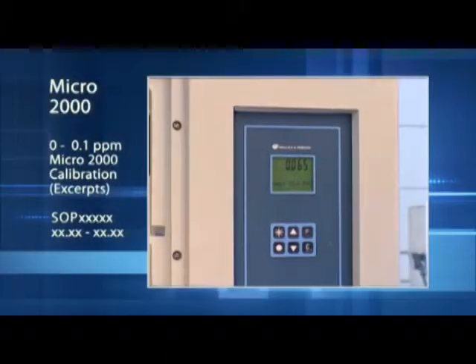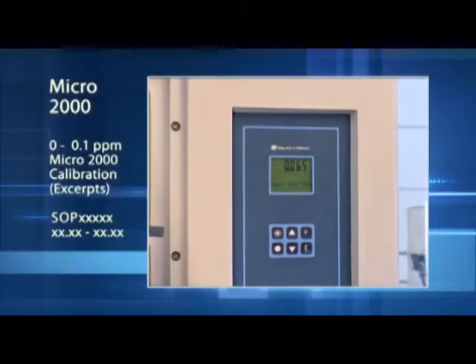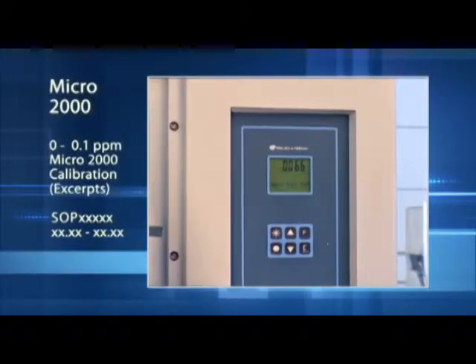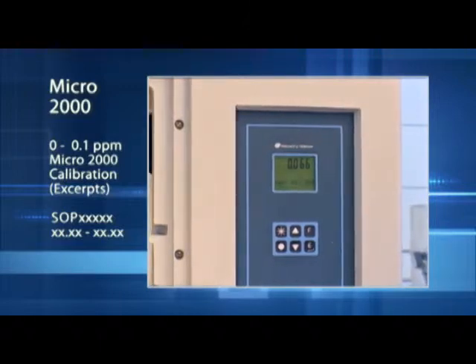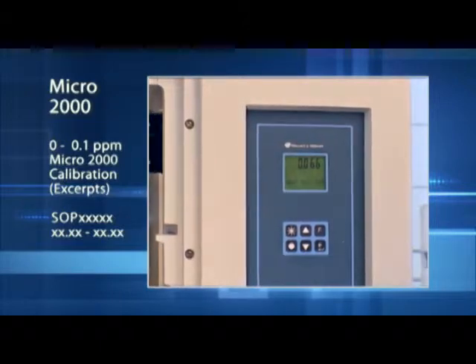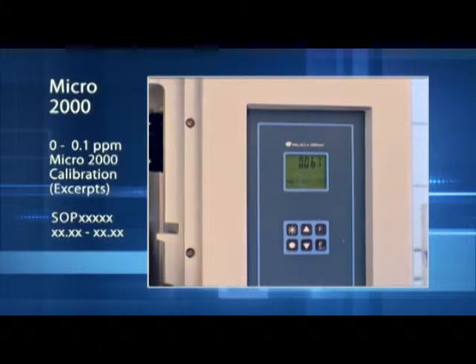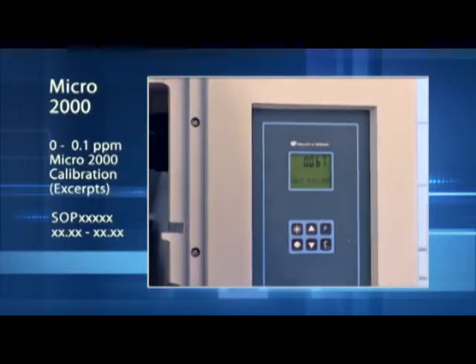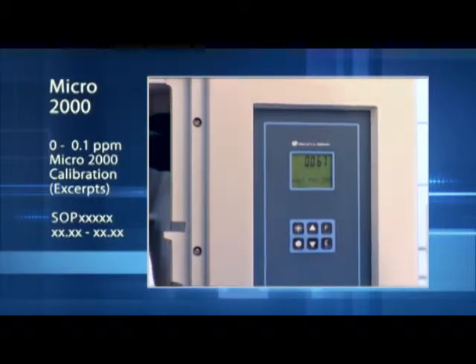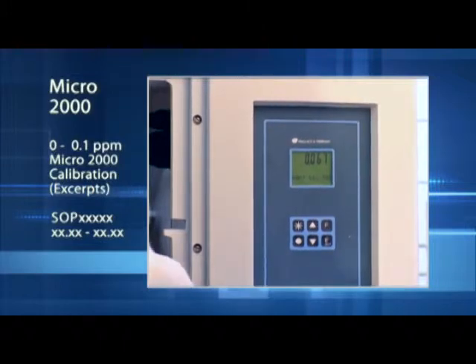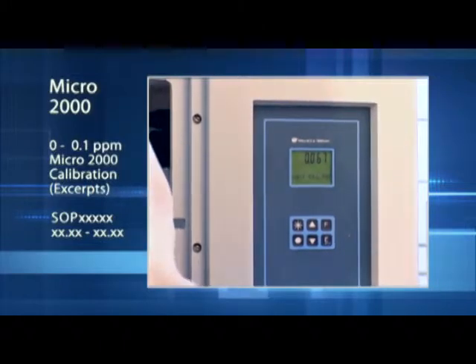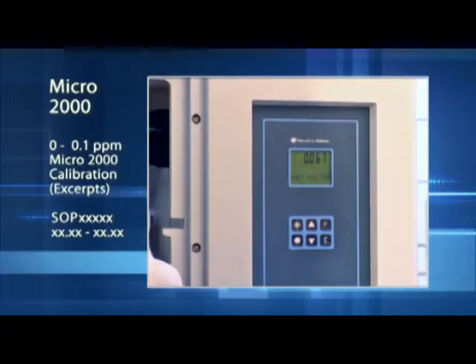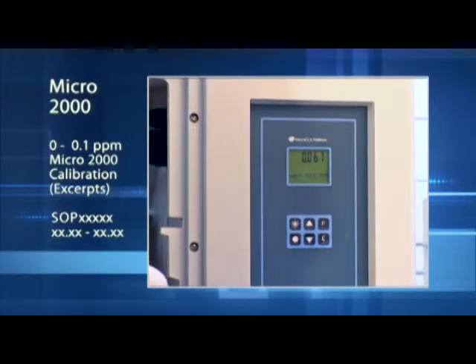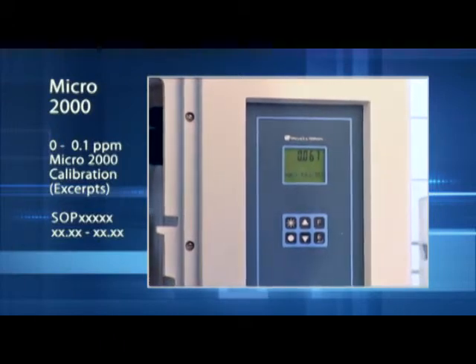So we've waited 15 minutes for the reading to stabilize on the Micro 2000. The display is showing 0.066 ppm. We calculated the solution should be 0.070 ppm. So we require a tolerance of 0.004 ppm, and we are within that. So the instrument at this time does not need any adjustment to its calibration.